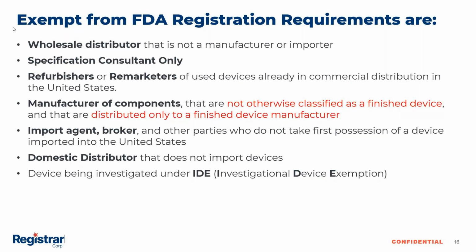Also not required for registration are specification consultants, refurbishers or remarketers of used devices already in commercial distribution, and manufacturers of components that are not otherwise classified as finished devices, where the component is distributed only to a finished device manufacturer. So you are only making, let's say, part of a device, a case, but that's all you're doing, and you send that over to the finished device manufacturer who uses the case to build the complete device. You don't need a registration.